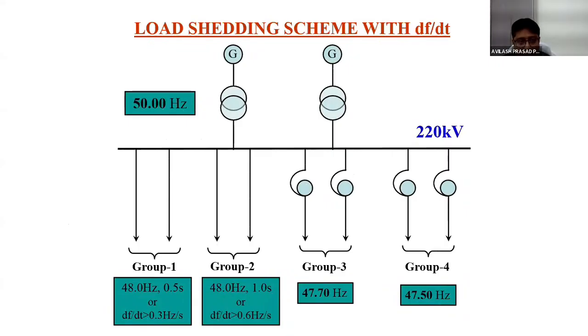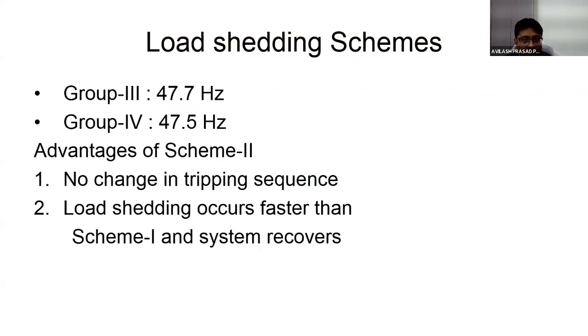Through a diagram, it can be understood. Group 1, 48 Hz, what I have shown. Group 2, 48 Hz, 1 second, df/dt greater than 0.6 Hz per second. Group 3, 47.7, and group 4, 47.5. So the advantage of this scheme is that there is no change in tripping sequence and load shedding occurs faster than scheme 1, and the system recovers.